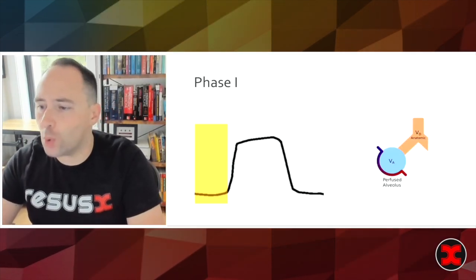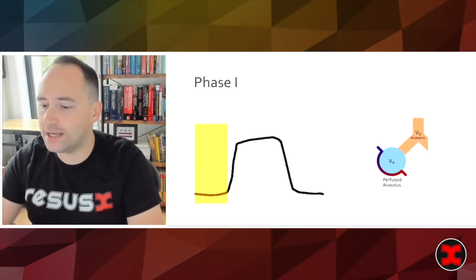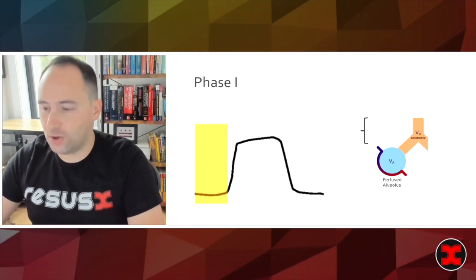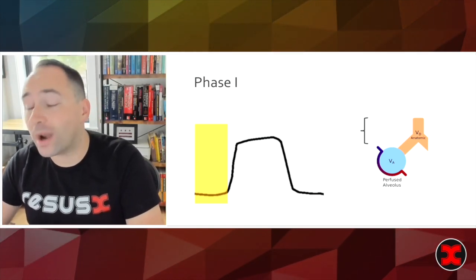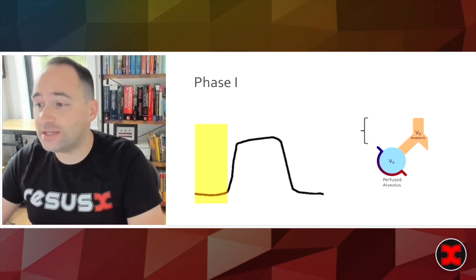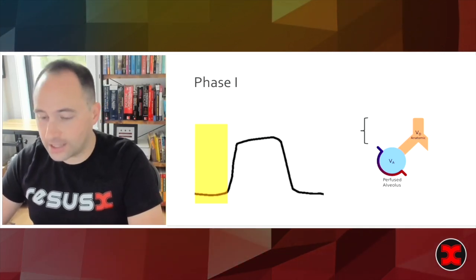So this is phase one. Phase one corresponds to the exhalation of pure dead space gas. So this is all of the gas from your central conducting airways or any equipment that is distal to your sampling site. Ideally this area or this phase should have no detectable carbon dioxide.